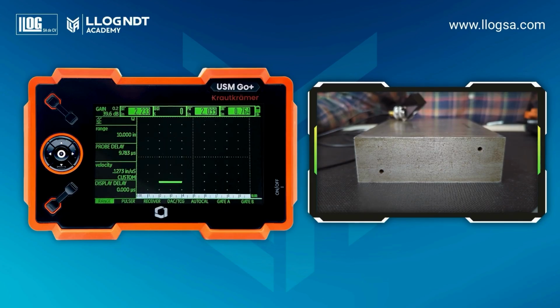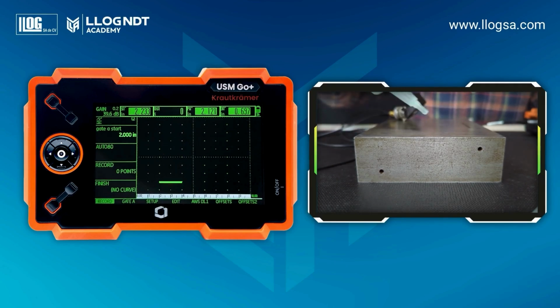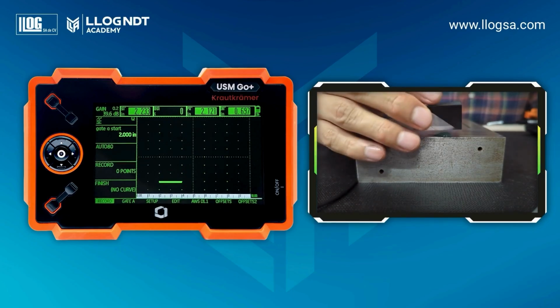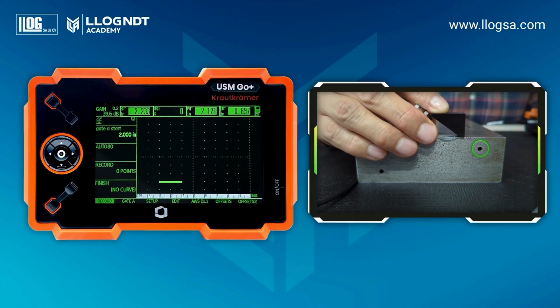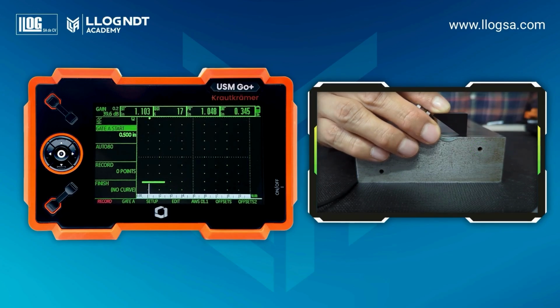Return to the A-scan and go to the DAC function group. Place the transducer aimed at the 1/8 inch diameter hole located at 1/4 of the block thickness. Position the gate on the echo and move the transducer back and forth until the maximum amplitude is obtained from the echo corresponding to the hole at 1/4 T.